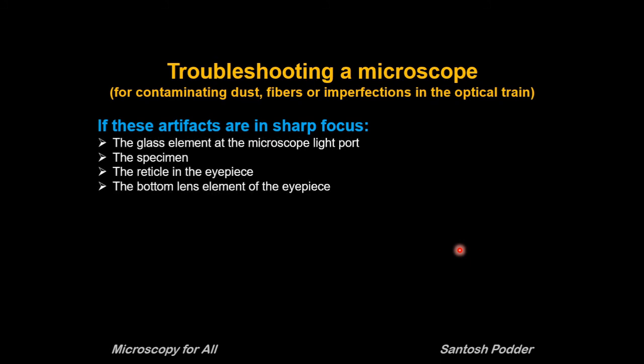Proper understanding of these illumination and image planes will help you troubleshoot the microscope, particularly for contaminating dust, fibers, or imperfections in the optical path. If these artifacts are in sharp focus, you should look near the surfaces that are part of the image-forming set of conjugate planes — for example, glass elements at the microscope light port. From my experience, I would not suggest putting your hand into this yourself; call an engineer to get it done.